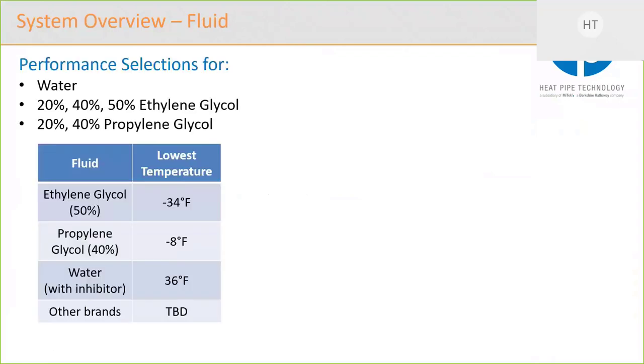Now, looking at the fluid, we've characterized performance for water. There are conditions when you actually don't need glycol. However, you still need an inhibitor to avoid corrosion. We've also characterized varying ethylene glycol percentages and varying propylene glycol percentages. And what we found is in our application, the performance doesn't change that much with glycol. It's really the viscosity, the resistance in the system that's changing. So for example, if you had a 30% propylene glycol application, we would size the pump for 40% just to make sure that we had enough pump head generated, but you would still get the performance that we'd be showing.